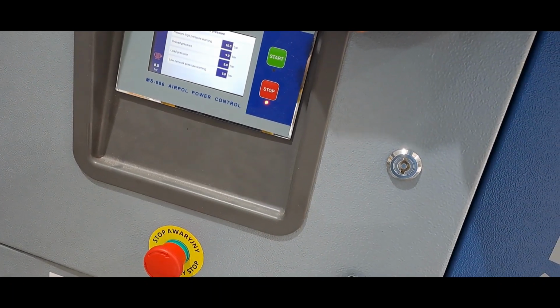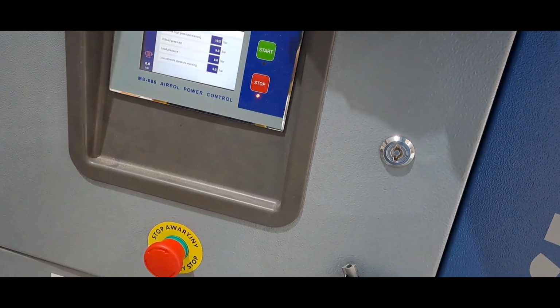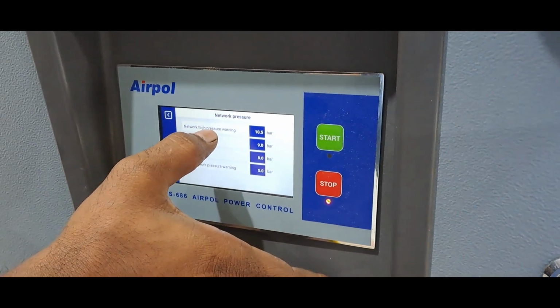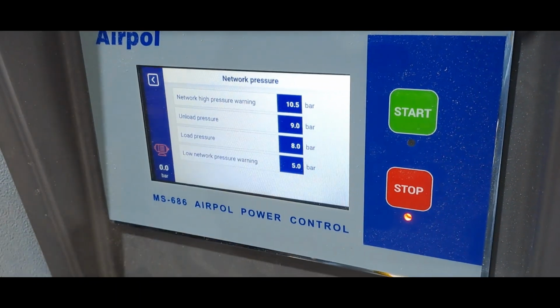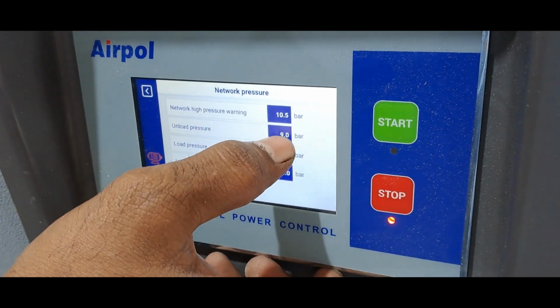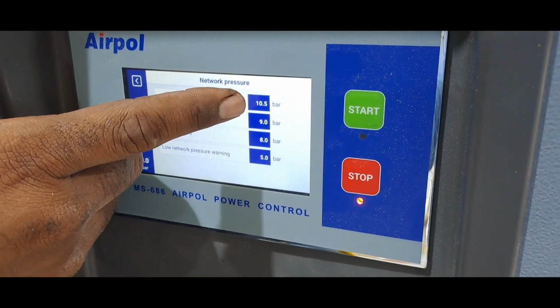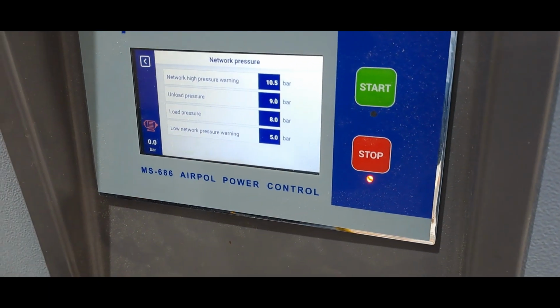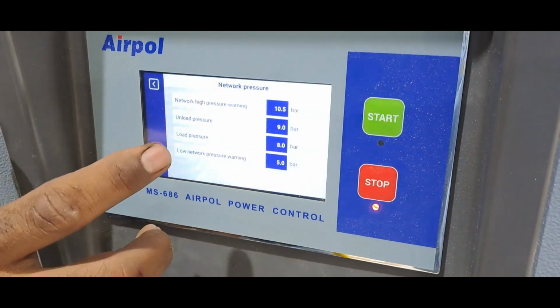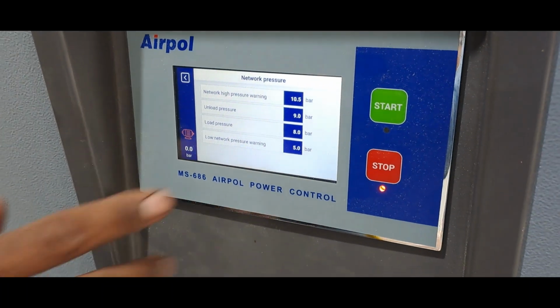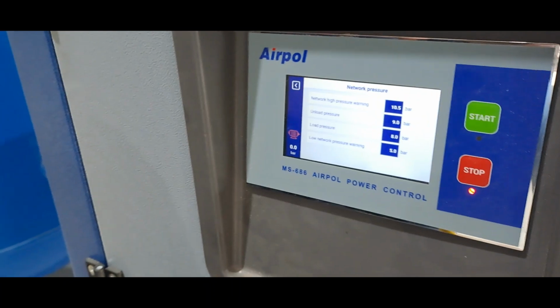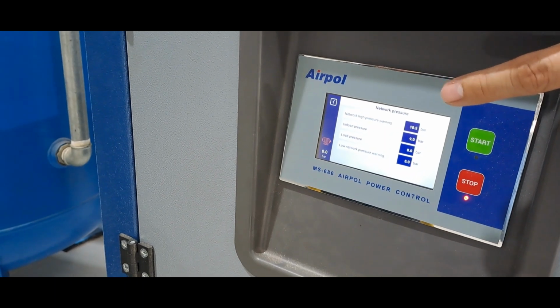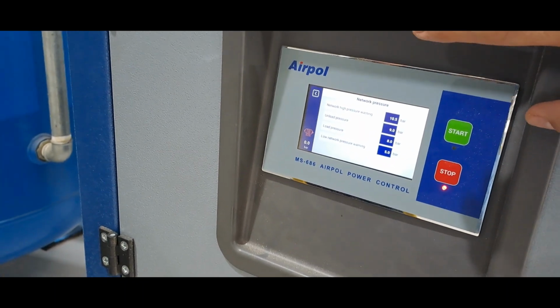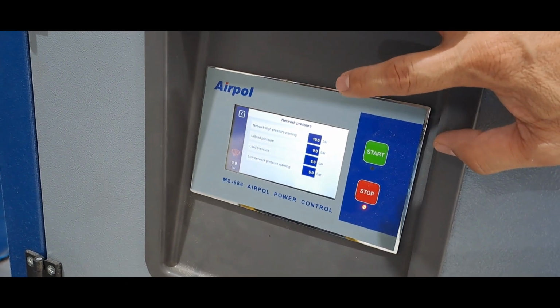This is configurable. It depends on your application. If you require 5 bar only, or 4 bar, or if it is industrial, 9 bar, 8 bar, it depends. You can configure. There is one more option here, network high pressure warning. This is set at 10.5 bar. If in case the compressor fails to unload at 9 bar and it reaches 10.5 bar, it will directly stop the complete system. It will directly stop the motor to avoid any explosion. Yes. Okay, so that is the secondary fail-safe mode. In case the first safety at 9 bar doesn't work, then the secondary cut-off pressure will engage.